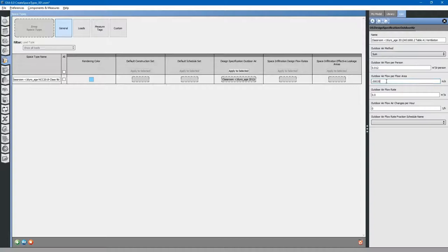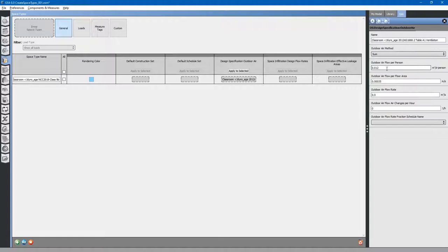The code says we have to sum those two. It's going to calculate the floor area ventilation rate and calculate all the people in the room multiplied by the per-person flow rate, then add those two together. If you have a different application where you're calculating the maximum, you would select that here, and EnergyPlus will calculate each one and choose the highest of the two. That's how you create a design specification outdoor air - essentially a ventilation rate.